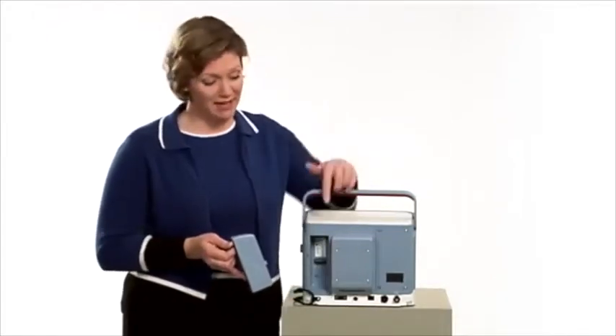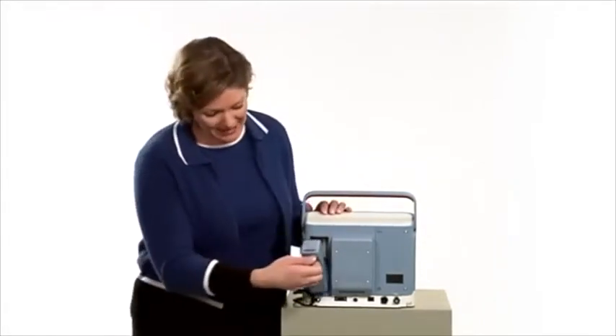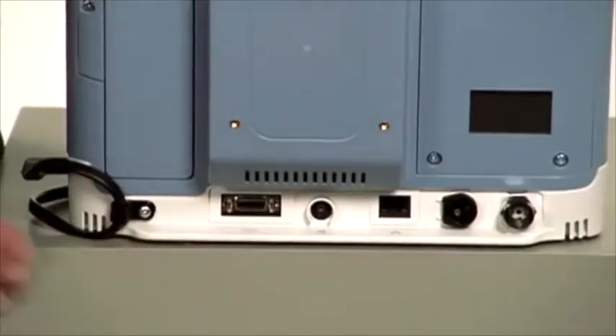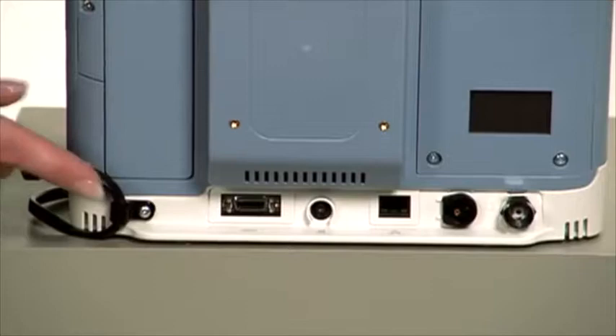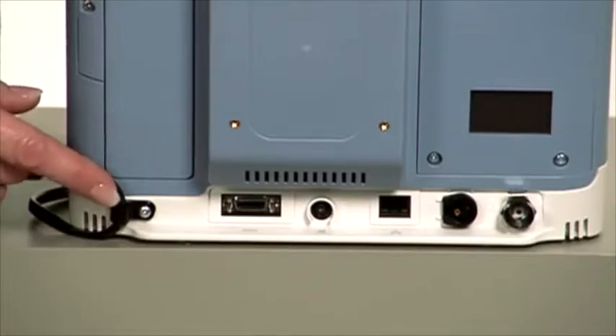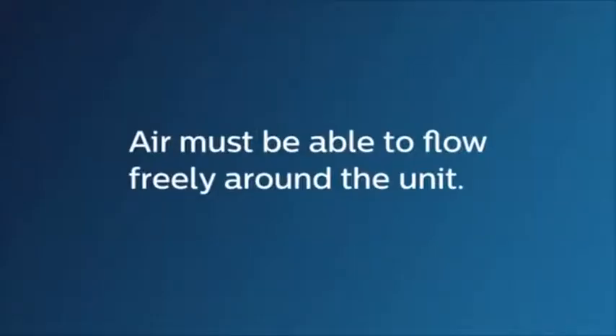On the other side of the ventilator is a detachable battery pack slot. A lithium-ion detachable battery pack is used to power the device and attaches here. Looking across the bottom, there are a number of connections and ports. You can secure the power cord using the cord retainer. Make sure that the air inlet port on the back of the device is not blocked and that air can flow freely around the unit. If the airflow is restricted, the ventilator may not work properly.